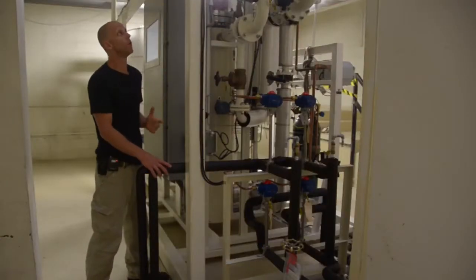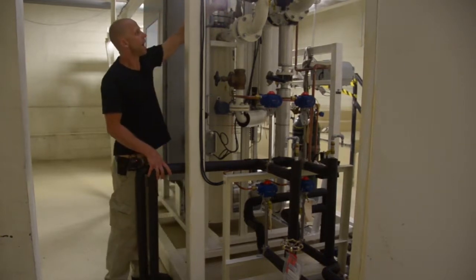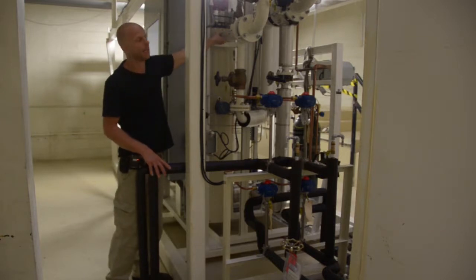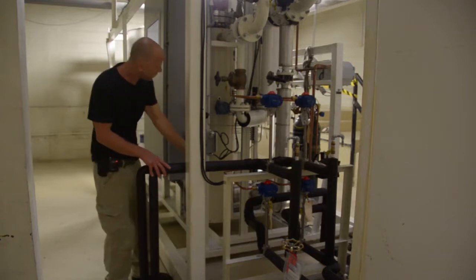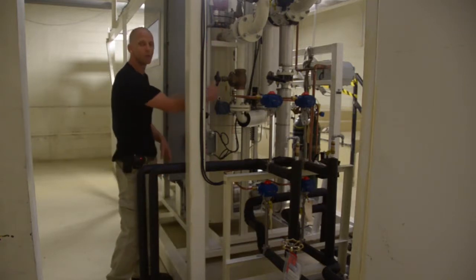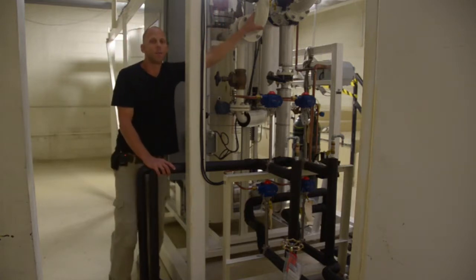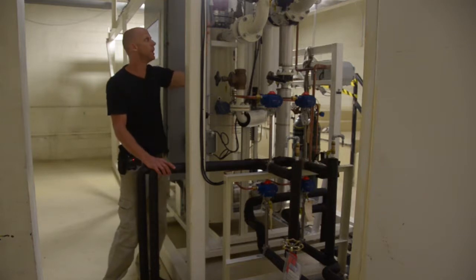Okay, so during the normal running of the plant, this line will be the waste nitrogen from the top of the column. And we will have waste nitrogen that comes down this line through a check valve and goes to a regen heater. Okay, the air is heated to a set point temperature, comes back out of the base of the heater and flows to our regen bed. Okay, so that's when the plant is making liquid, and we have a supply of waste nitrogen from the top of our distillation column. It's excess nitrogen. It's a nice, safe, inert gas that we can use for heating and regeneration.